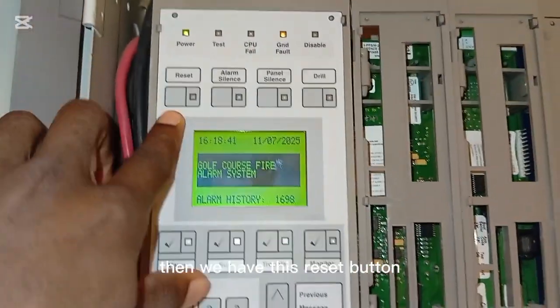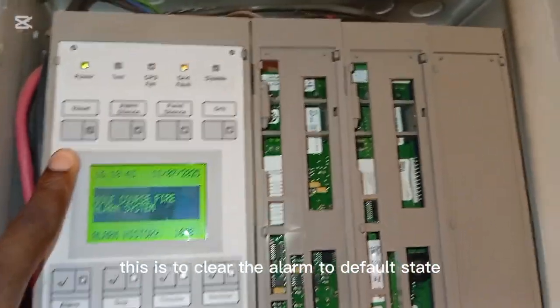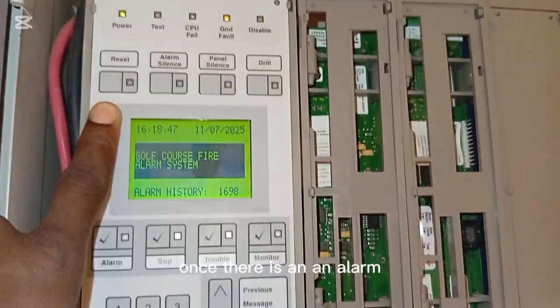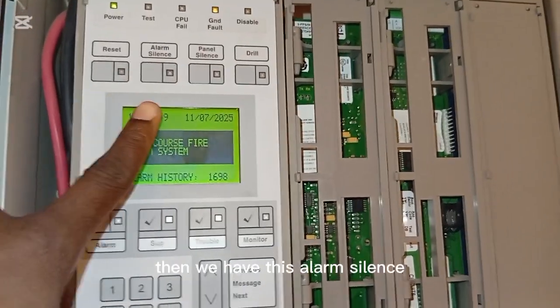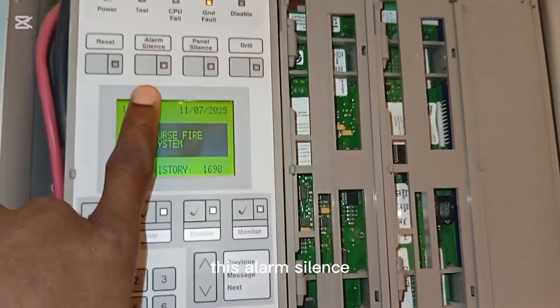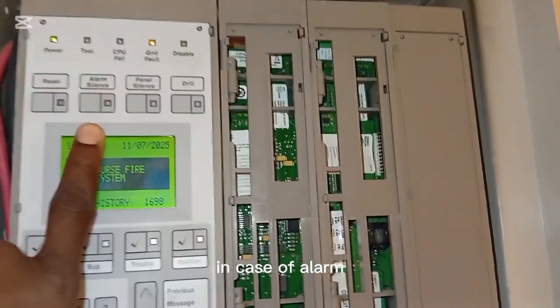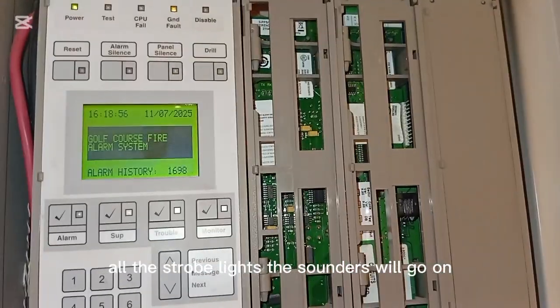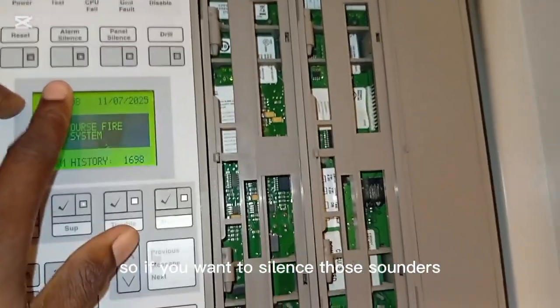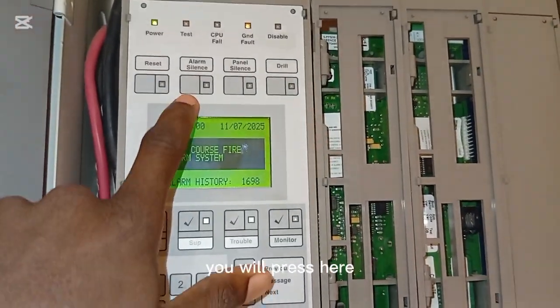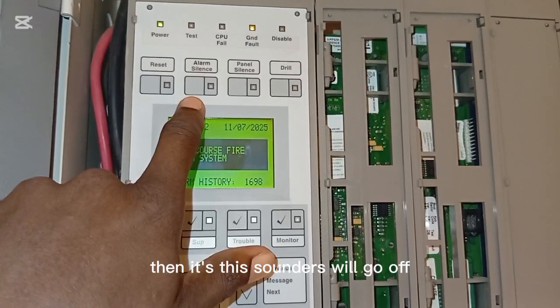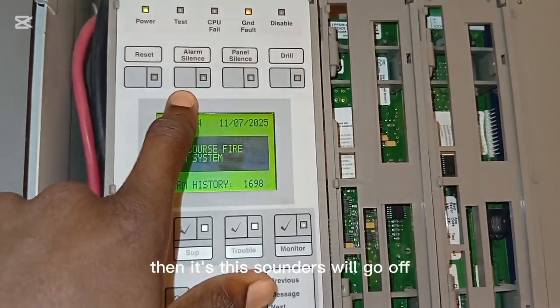Then we have this reset button. This is to clear the alarm to the default state, to return the system back to normal once there is an alarm. Then we have this alarm silence. In case of alarm, all the strobe lights and the sounders will go on. If you want to silence those sounders, you will press here, then these sounders will go off.